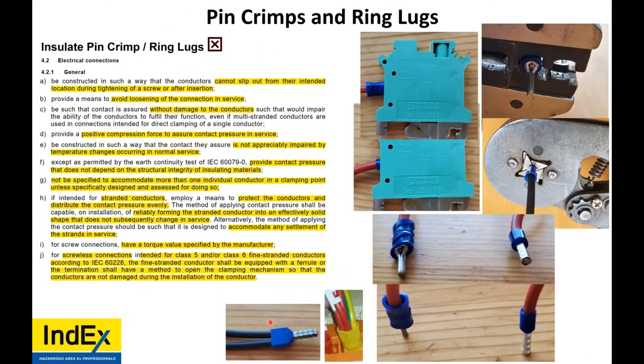Now, why are insulated pin crimps no good according to the standards? Well, -7 and -15 clearly call it out, and I can show you in my side-by-side comparisons that I did the other day. Cannot slip out of the intended location during tightening. Well, in the terminal for a ferrule, it has a sloped collar. It will not be crimped on. The problem with the insulated pin crimp is it cannot always get all the way into the terminal.